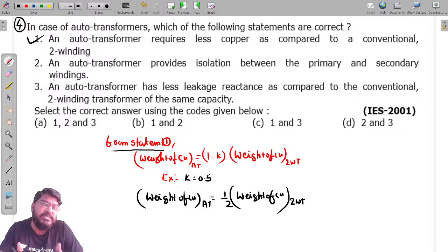So now you cannot get perfect isolation between the primary and secondary by using auto transformer. This is one of the disadvantages or limitations of the auto transformer. So auto transformer cannot be used as isolation transformer wherever isolation is required between the LV winding and HV windings. So that statement is wrong.